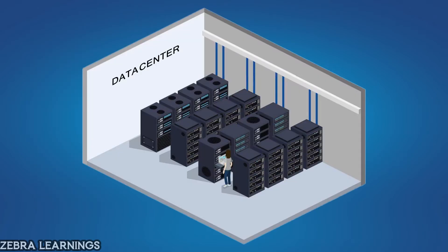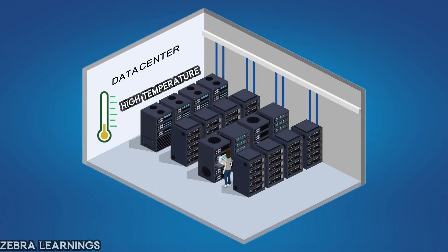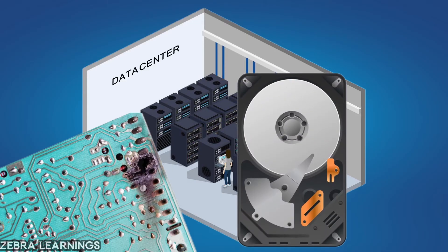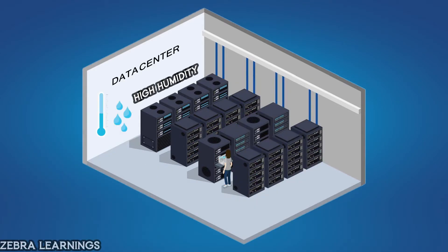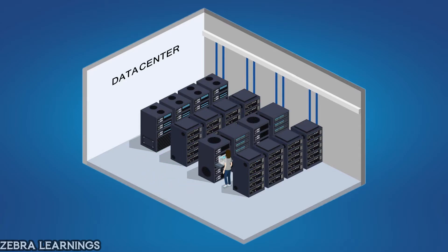Let's take data centers as an example. A data center is like the brain of a company — all its data are stored here. If a data center overheats, the performance of the equipment within it could slow down, and sometimes the whole data center might even shut down. The excess heat also increases the chances of damage to circuit boards and hard drives. Excessive humidity can lead to condensation, forming water droplets that might fall onto the electronic equipment, potentially causing damage. On the other hand, low humidity levels can increase static electricity, which can also damage sensitive equipment. These issues can result in significant financial losses for companies — according to estimates, data center-related issues cause billions of dollars in losses worldwide each year. To avoid these problems, data centers use PACs.